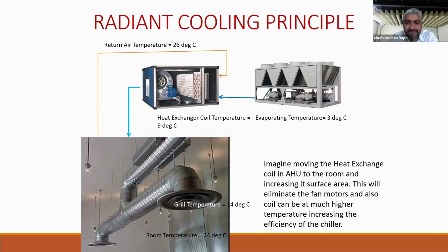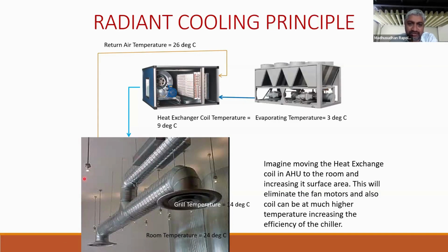And air is pumped in through the ducts. So radiant cooling doesn't change the need for the high side equipment, or a chiller. However, it brings efficiency there, but changes the way we distribute the cooling - it eliminates the need for an air handling unit or a duct. Imagine the coil you see in the air handling unit: if I were to remove that and bring it into the space being cooled, spreading it all over the ceiling, then you wouldn't need this fan motor.